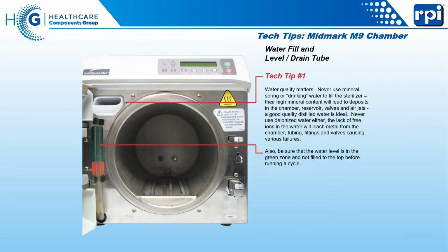Well, here's what the customer had done. The guy had left the machine with the water at the proper level. It's supposed to be about 1 inch to 1.5 inches below the top of the green. But the technician said, oh, look at that, that's just like halfway up. That doesn't sound right to me. So they filled it up to the very top of the green line. And what happens is when the machine vents back into the reservoir, it dumps all that steam, it bubbles the water in there. The bubbles get transferred out the front of the machine, and the water in this tube literally splattered out and all over their counter. Now, the technician said, that's impossible, my customer wouldn't do that, but I disagree with him. So please remind your customers to fill only to 1.5 inches, otherwise they get to clean the counter.